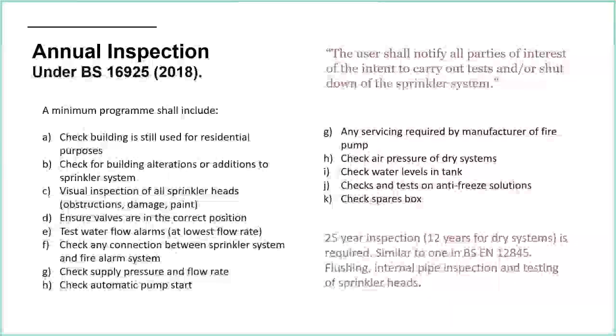The user shall notify all parties of interest of the intent to carry out tests and/or shut down of the sprinkler system. Again, for residential buildings, there should be some communication with the residents. You could argue if you're doing testing and there are going to be no alarms being sounded, then maybe you don't need to inform them. But I always think it'd be a good idea. Maybe something goes wrong. Maybe you thought you were going to isolate an alarm, but in the end you didn't, and so an alarm is sounded. It's just good to keep people informed, and particularly if the sprinkler system is off, then they definitely need to be informed because they are relying on that sprinkler system for purposes of life safety. So if that sprinkler system is off, then they are at more risk than they were before.